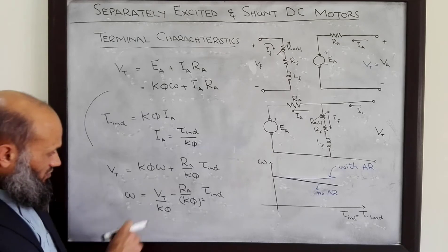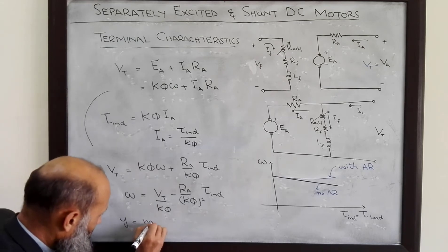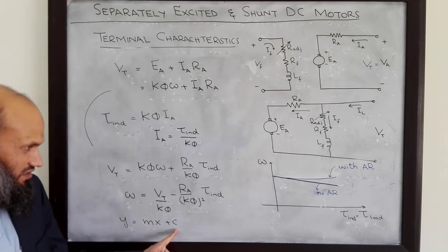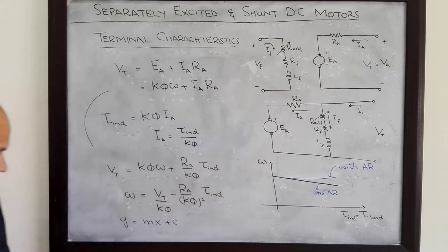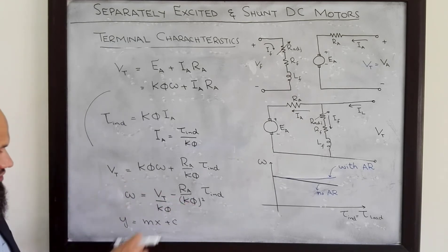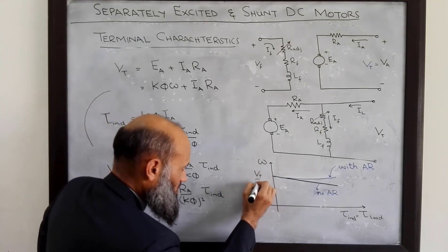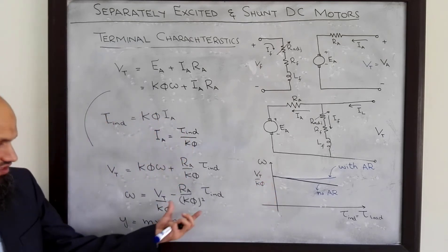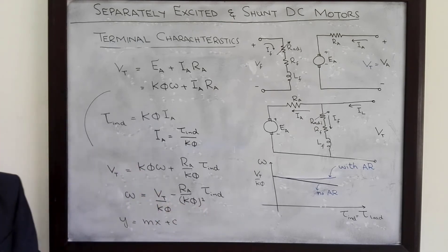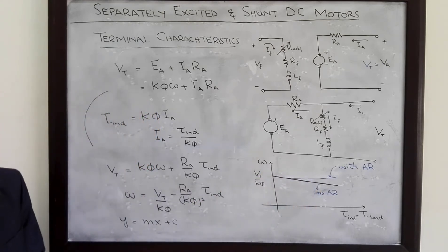This equation is quite similar to the equation of a straight line, y = mx + c, where m is the slope and c is the vertical intercept. Comparing, the vertical intercept is Vt/(Kφ) and the slope is negative — Ra/(Kφ)². Therefore, the torque-speed characteristics are described by a straight line with a negative slope.